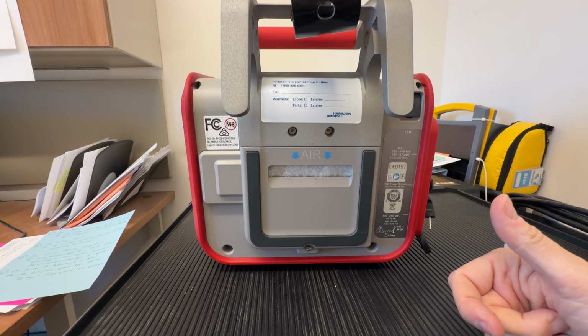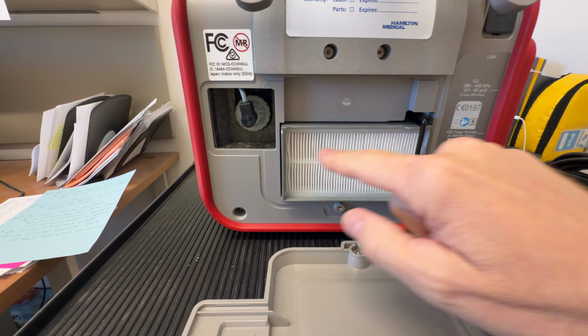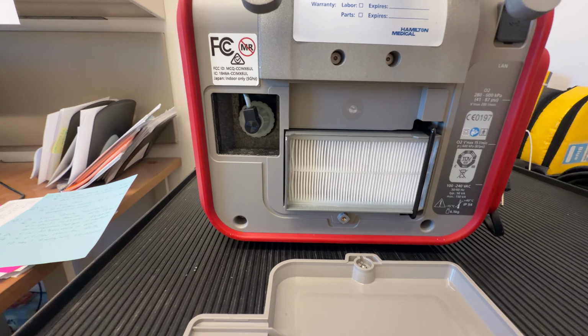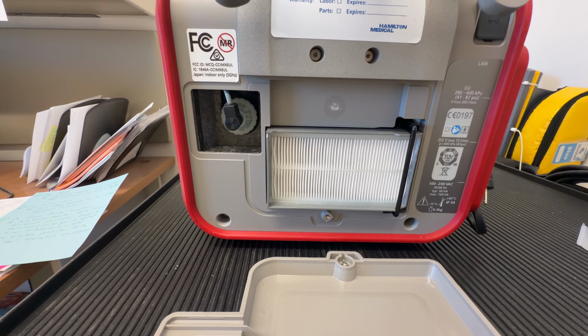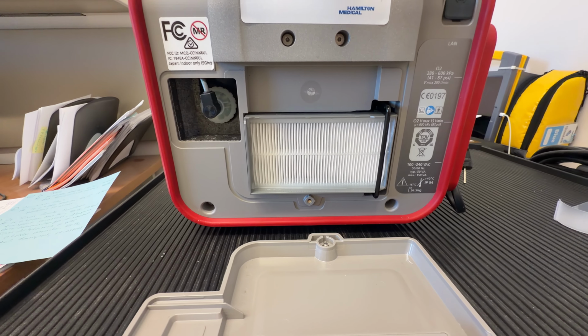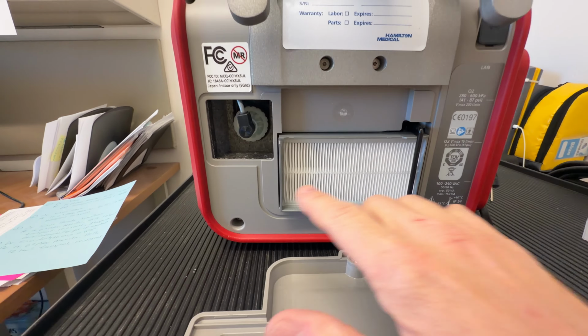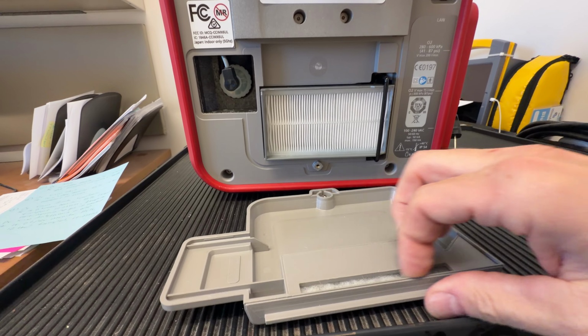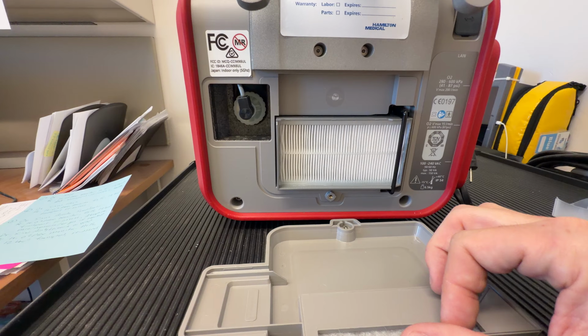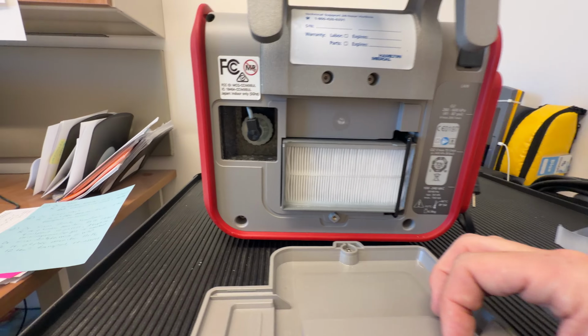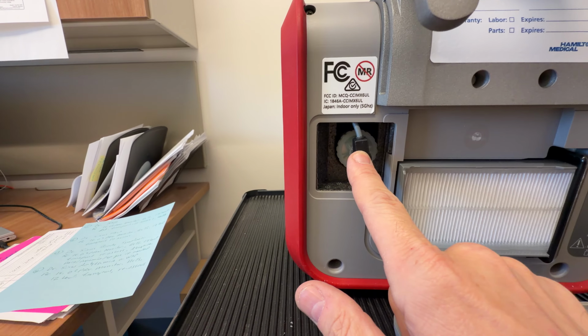However, to access some of the internal components in the back here, there's just a flathead screw. You just unscrew that, and then this cover comes off, and you can see you have this filter here. So you want to just check this filter. I would say every time you do your preoperative checks, in addition to your vent circuit check and your oxygen sensor check and your leak check, just pop this off real quick, make sure the filter looks good, make sure there isn't anything obstructing this outer filter here. And if you need to change the oxygen sensor, this is the oxygen sensor.